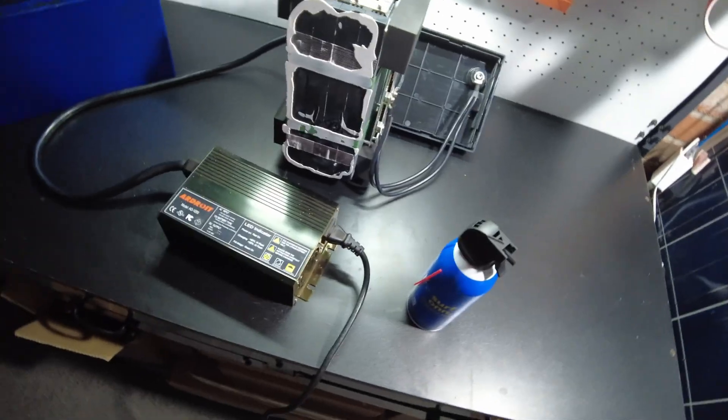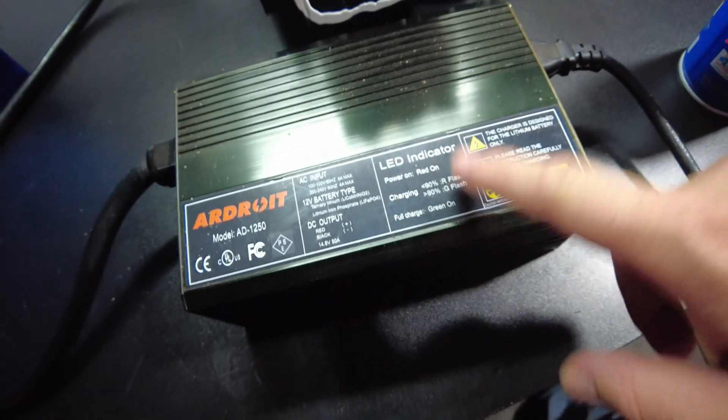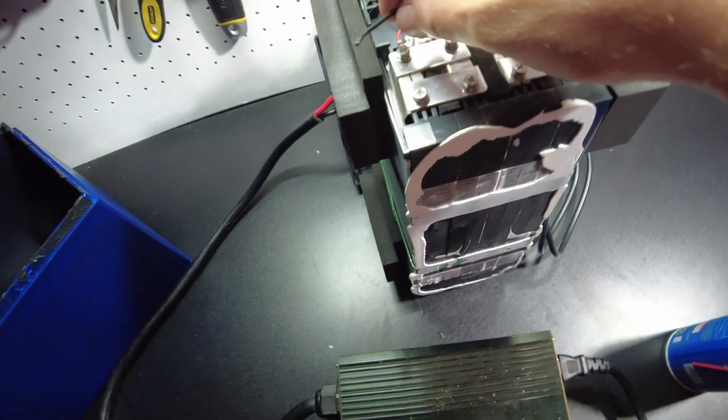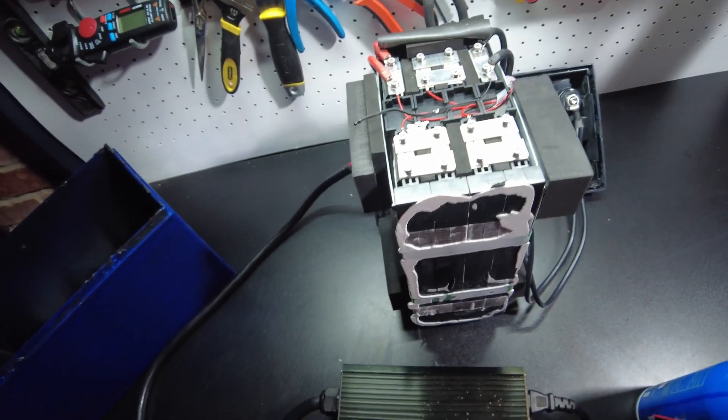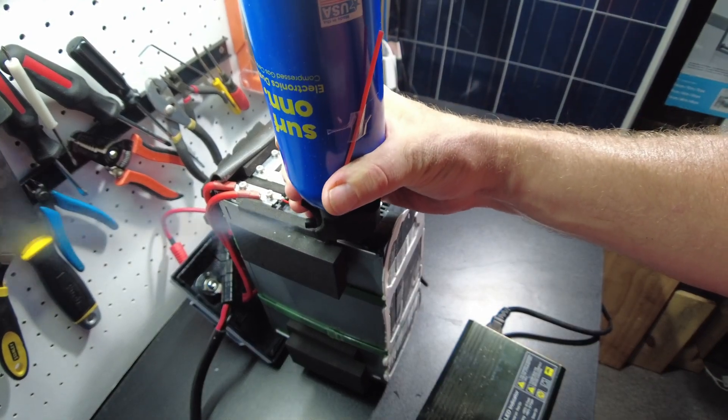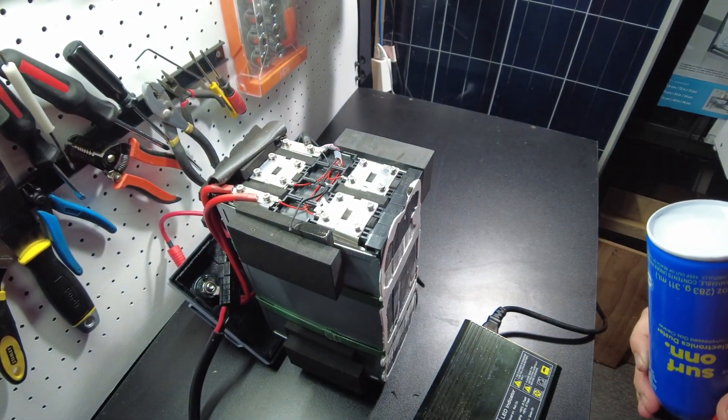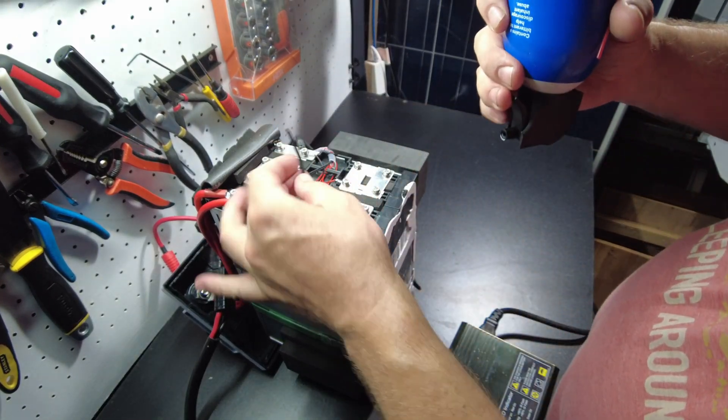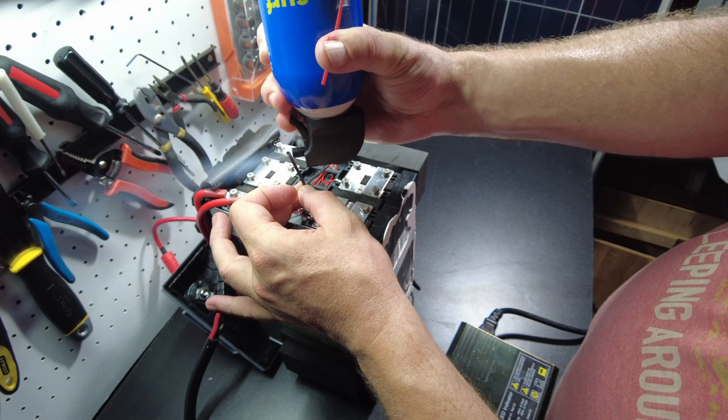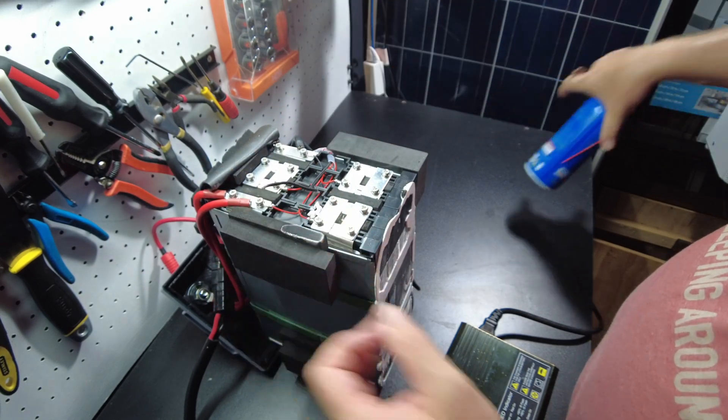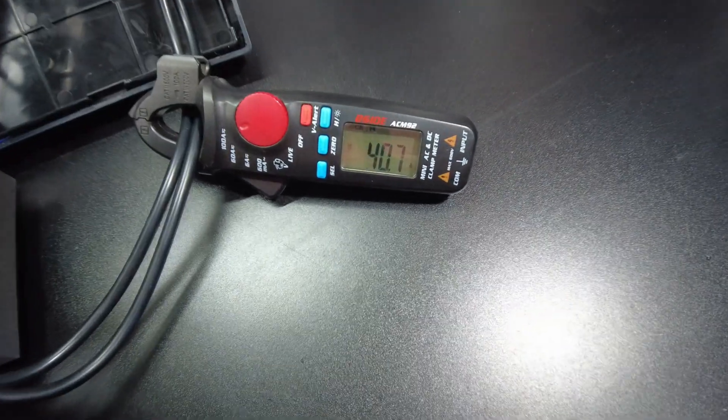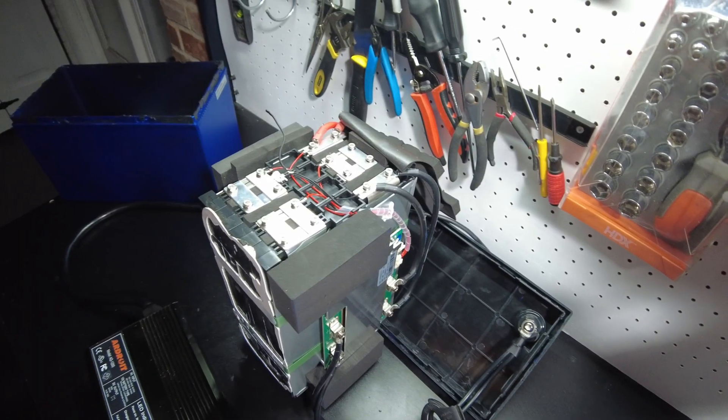Alright. So, I got the charger hooked up to the battery. We're going to plug the charger in now. We should hear the charger start. Okay. There it is. So, if this has low-temperature protection, when I freeze up this thermal sensor here, we should hear this go off. Nothing on that round. Let's try again. Nope. Still going. We're still doing 40 amps there. Let's try this again.